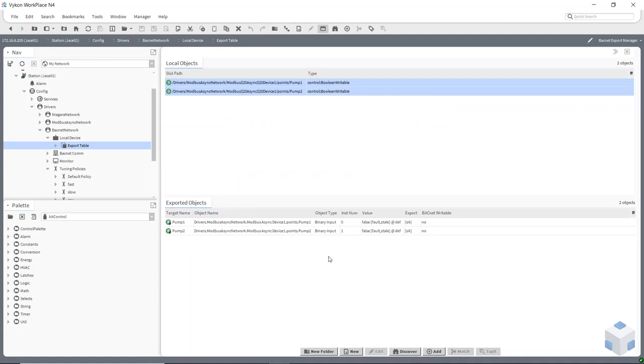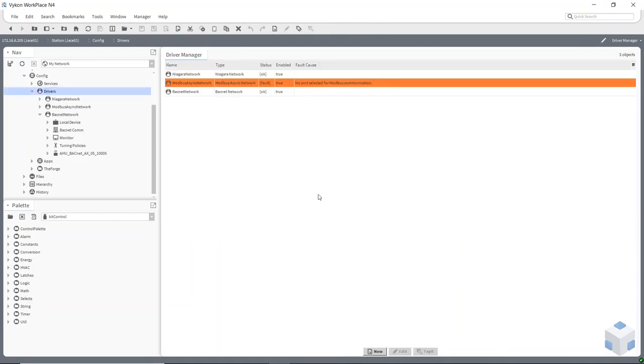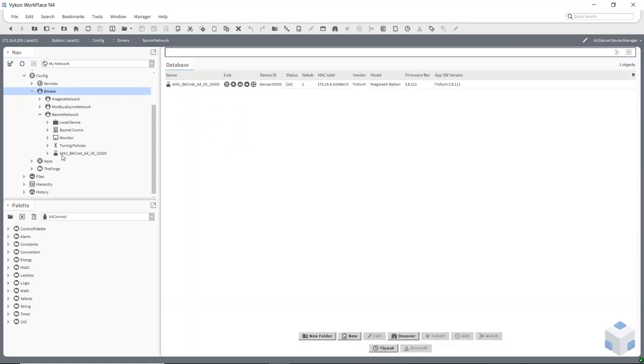Okay, so one more final thing just to show you quickly, because it's actually a question that comes up a lot in tech support, is how do I add a 485 network, a BACnet network? So you don't do what you might think and add another BACnet network. You actually go into the BACnet network you've created already, which defaults to IP. That's why when I set this IP one up, I already had an IP port on there.